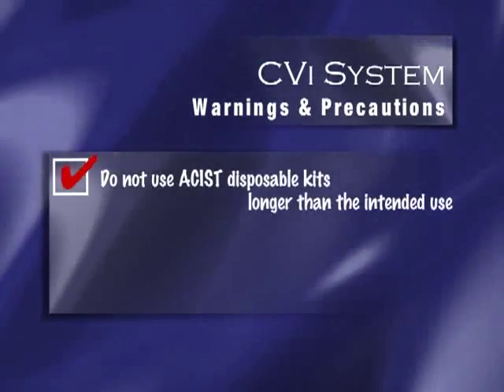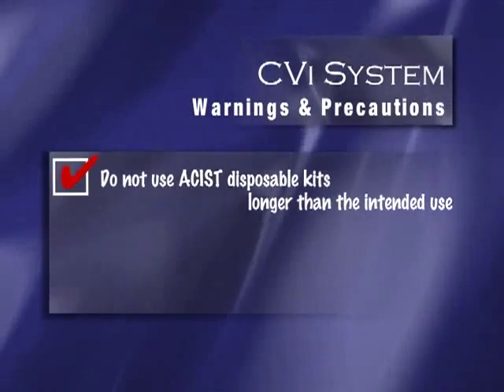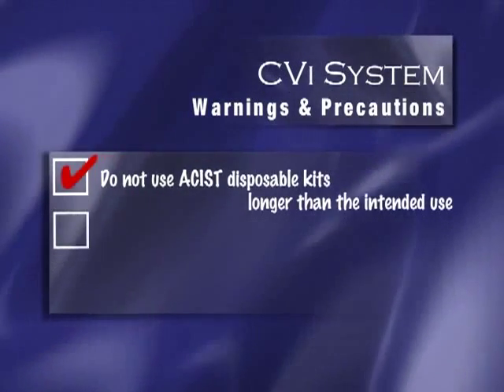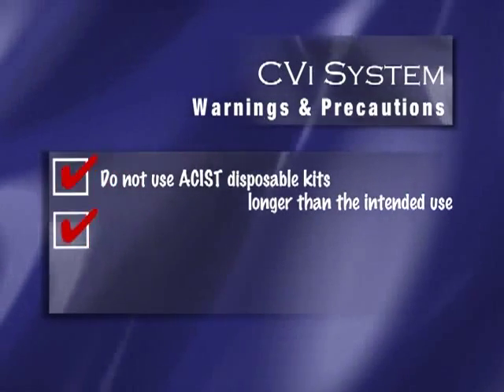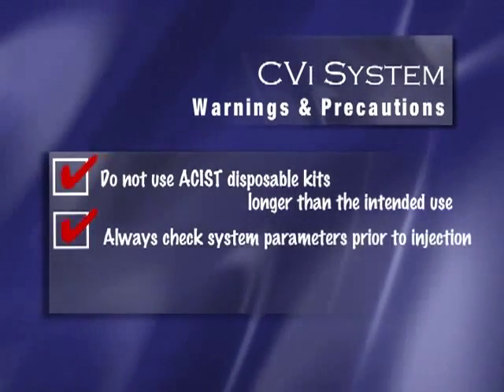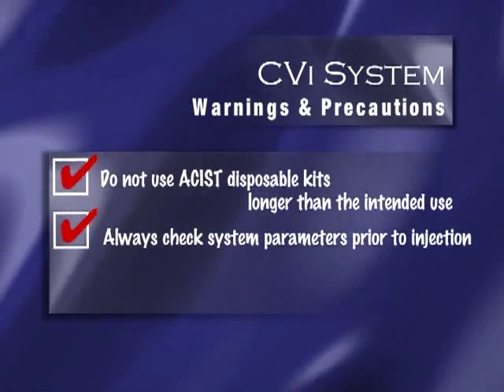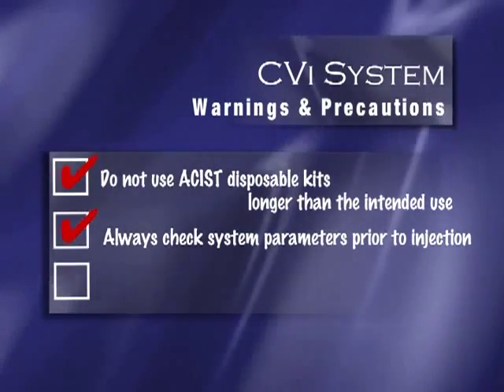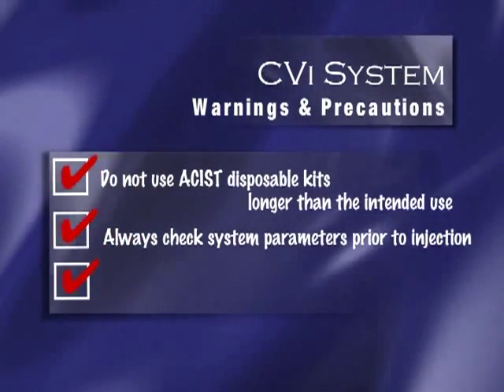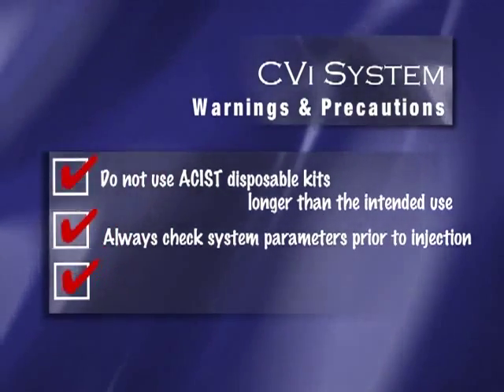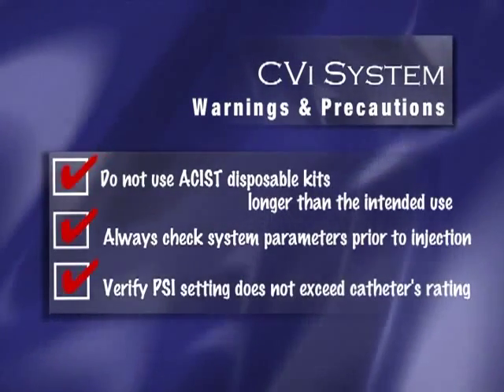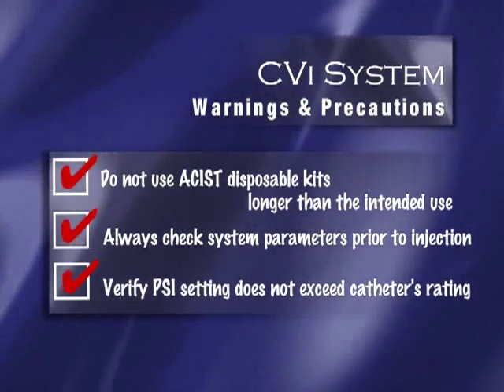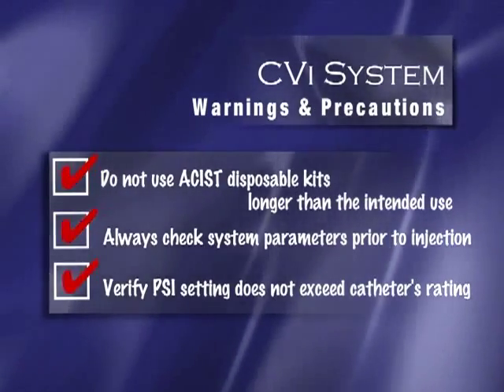A few precautions with the ACIST system. Do not use the ACIST disposable kits longer than the intended use. That is single use for the hand controller kit, single use for the manifold kit, and 5 times use for the syringe kit. Always check the parameters for the appropriateness of the injection. And remember, the flow, volume, pressure, and rise time is the maximum limit that you can achieve with that injection. Always verify that the pressure setting does not exceed the catheter's recommendation.